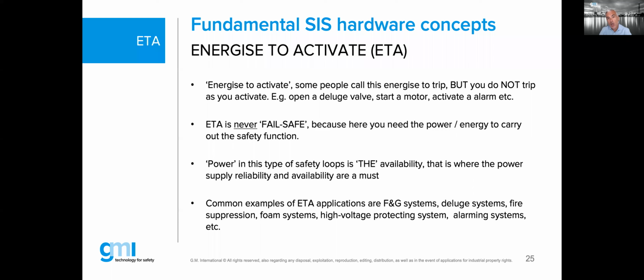Right, let's go just the opposite in our, let's say, philosophy. Now we're going to energize those final elements, those outputs, to do something. And I do know in the very old standards, in the very old seminars, webinars, training we have done, even myself, we used to call this energized to trip. And basically, energized to trip, I always had some trouble to pronounce this because I said, how can you call something energized to trip? When you do not trip, you just start the functionality. I'll give you an example. Typically fire and gas, typically sprinkler, deluge systems. You start the pump, you have to have the water available, you have to open the sprinkler to do something. So how can you call energized to trip a pump that you start to activate the functionality? It was very strange to me.